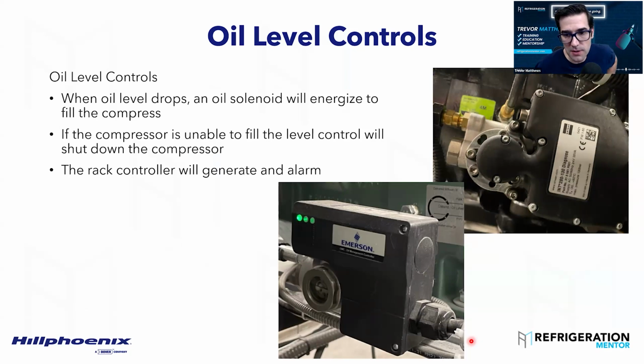Something just jumped up in the chat by Dimitrios. Gained some experience in Iraq using PEG 68, and somebody added POE 85, and now the oil kept foaming and confusing the oil level sensors, which was always causing them to trip out. I heard about that before too. So this is where you got to do oil analysis, oil lab tests. Have you talked to many of your contractors about doing not an acid test, an oil sample test? Do you guys get your contractors to do that, or the contractors out there?